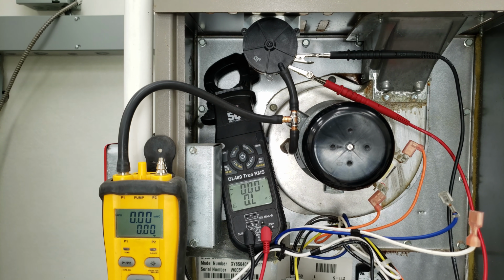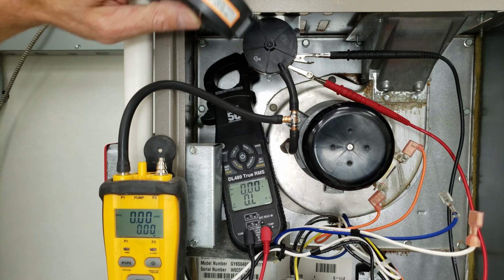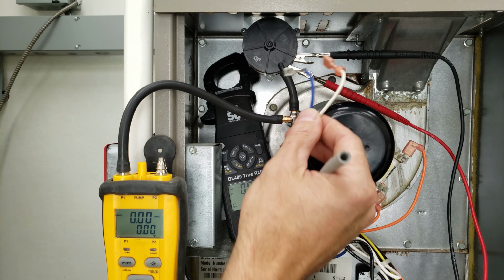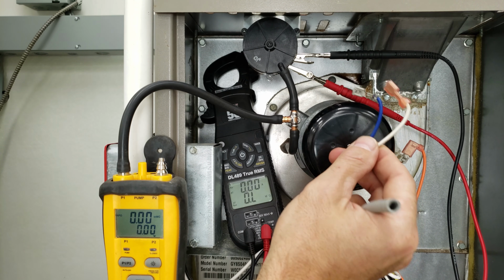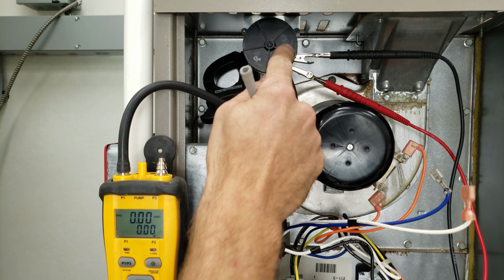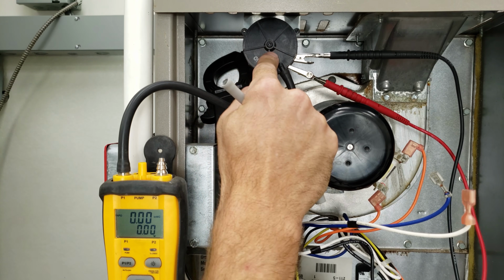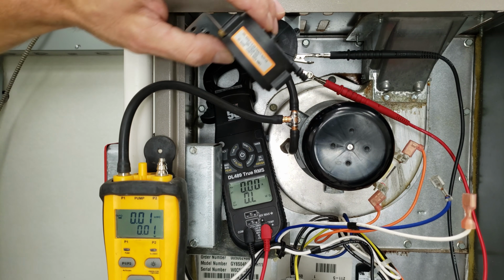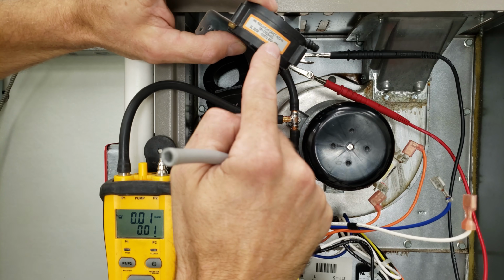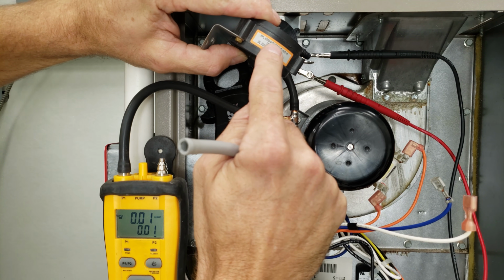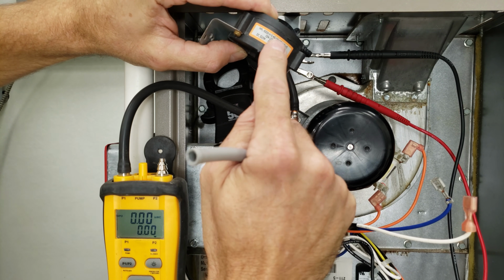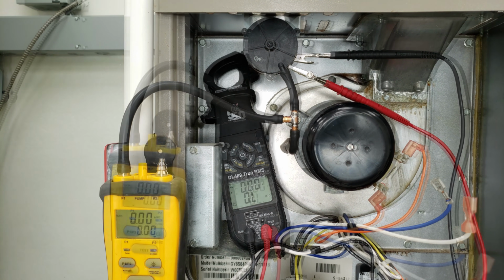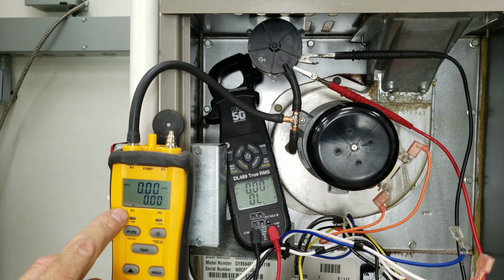So now we're going to turn this furnace on in heating mode, and you know I've disconnected these 2 wires that go to the pressure switch. You could also just measure voltage across the switch in order to see if this closes while the furnace is running. This pressure switch is the same as this one right here, and it's 0.45 inches of water column as far as the spring pressure inside. So our water column manometer is on P1, which is right here, and you see it's zeroed out. And so now we'll turn the power onto the furnace, and the thermostat is set on heating mode.